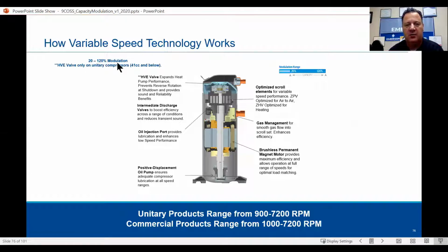Ranges are from 20 to 120% modulation. The HVE valve on the unitary compressors of 41 cc and below. So the HVE valve is nothing more than a check valve. It reduces the volumetric efficiency. So that's what it does. It's a check valve so we don't get discharge gas back into the scroll set, causing that volumetric efficiency loss.